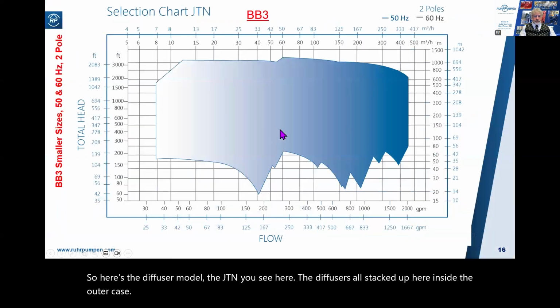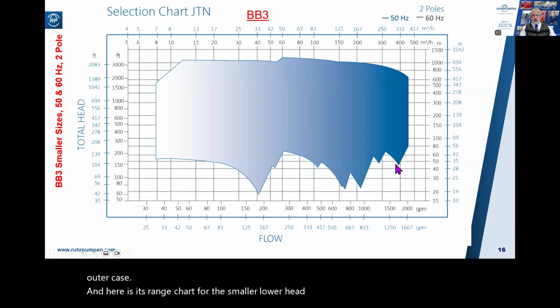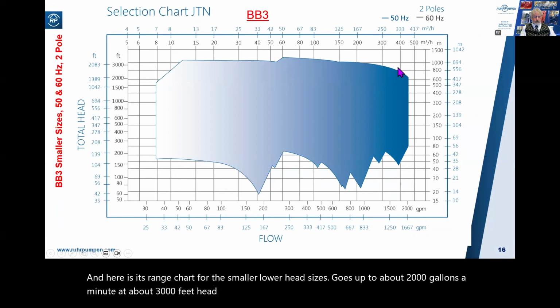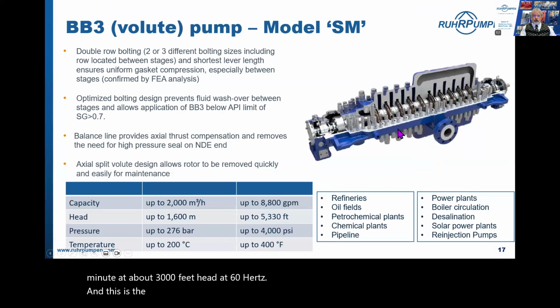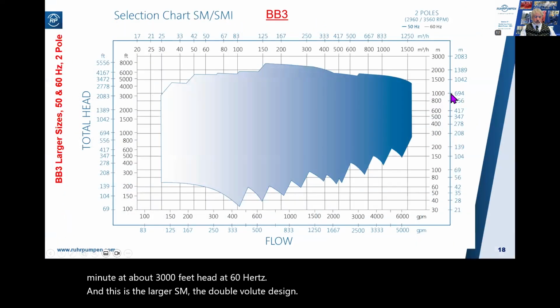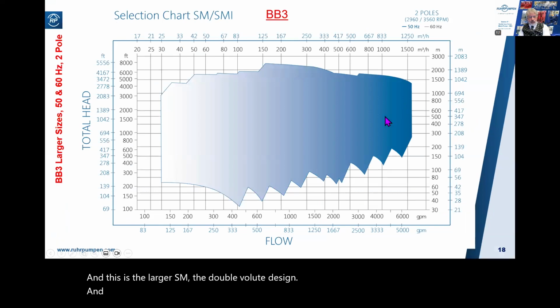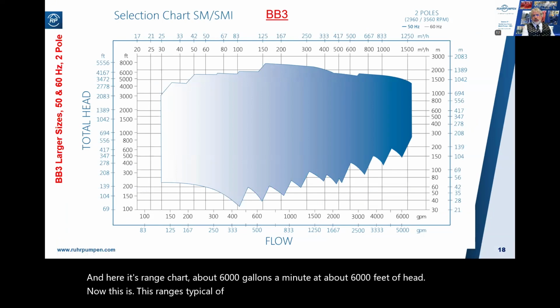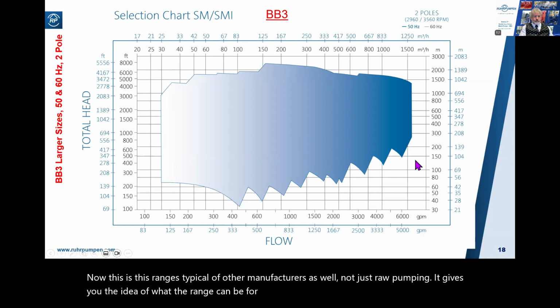And here is its range chart for the smaller, lower head sizes. It goes up to about 2,000 gallons a minute at about 3,000 feet head at 60 hertz. And this is the larger SM, the double volute design. And here is its range chart, about 6,000 gallons a minute at about 6,000 feet of head. Now, this range is typical of other manufacturers as well, not just Ruhrpumpen. It gives you the idea of what the range can be for these pumps.